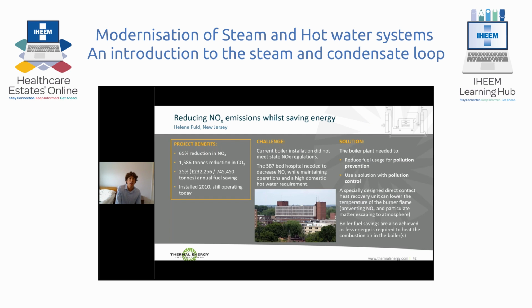We have an example of the application of this technology from the US, in New Jersey, at the Helene Fuld Hospital. An expansion to the 587-bed hospital following the relocation of a campus required additional heat to meet the operating needs of the hospital. Initially, the option to add a fourth boiler was considered, which would have cost $800,000 and increased CO2 and NOx emissions, which they're already at the limit at for the site. Additional constraints: the limited space available to install the new equipment within the existing hospital power plant.